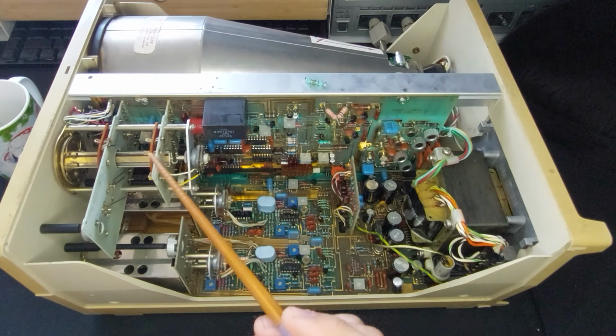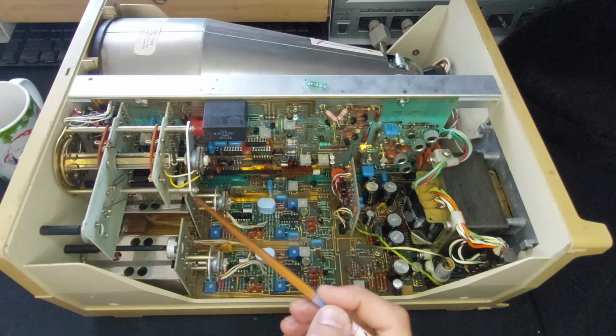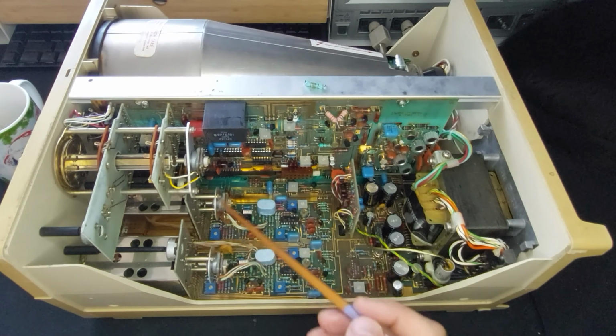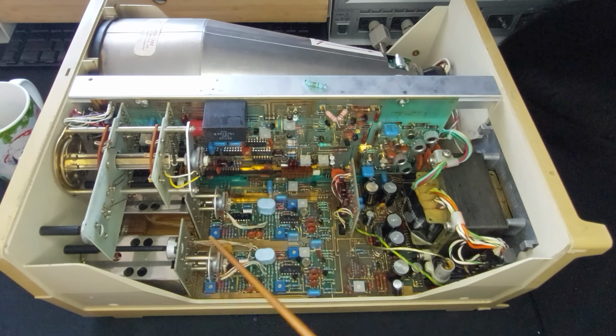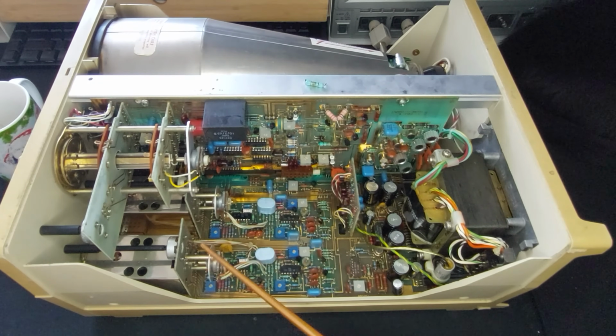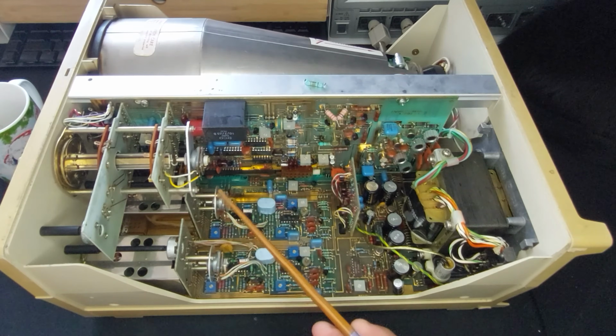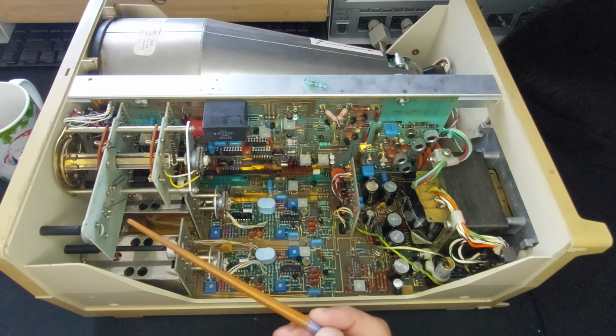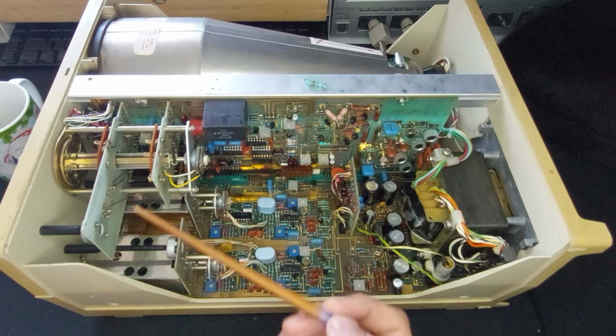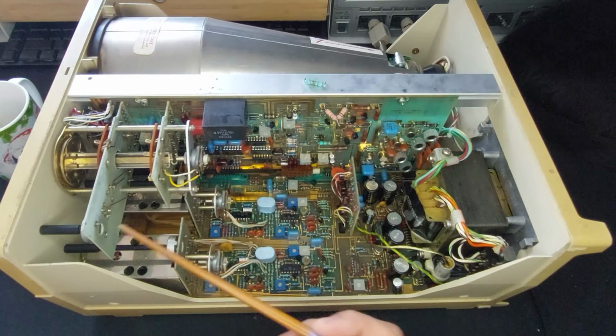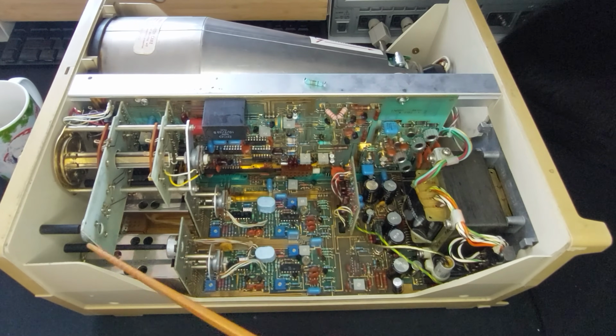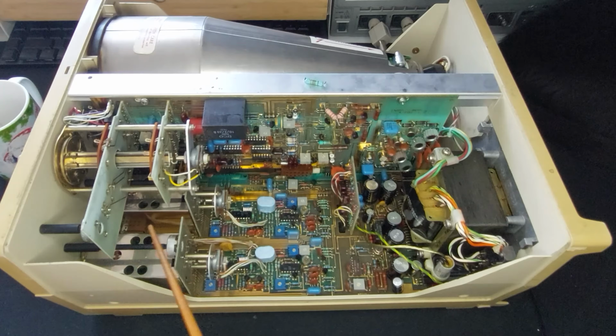And we have the input switch. This is for the time base, and these identical modules are the input attenuators for the vertical basically. And we have offset position for vertical, and we have another control which is the horizontal position. This had almost no effect on the sweep, so that's how I figured out what was wrong with the thing.